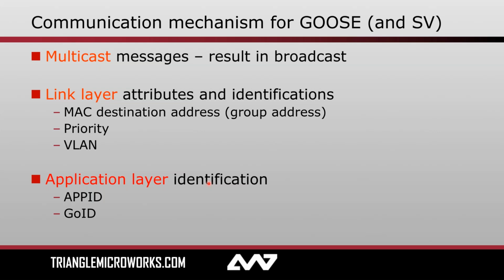Also, another two tools that you have at your disposal are application ID and GOOSE ID. So GOOSE ID does need to be unique throughout your system. If I'm publishing 75 different GOOSE messages across 25 different devices, then each individual GOOSE stream, if you will, needs to have a unique GOOSE ID. But this is something that can be set by you. It can be a string that makes sense to you, just a name that you can use to identify that GOOSE message later on.